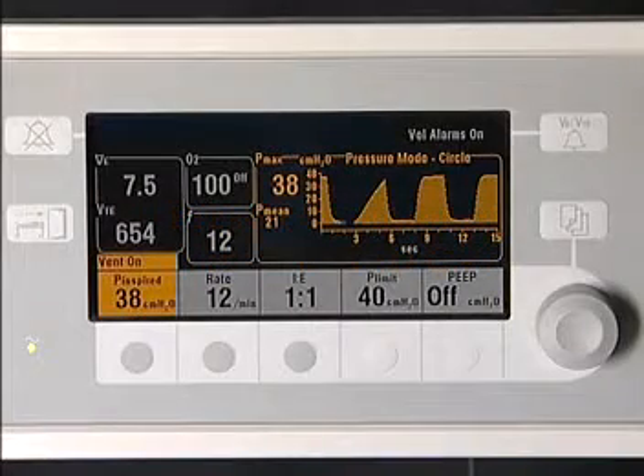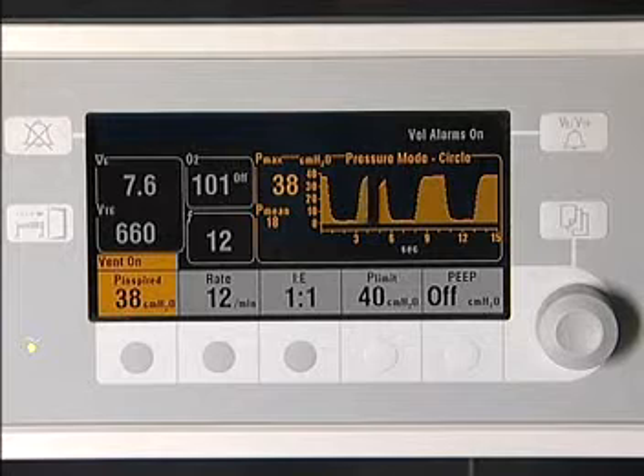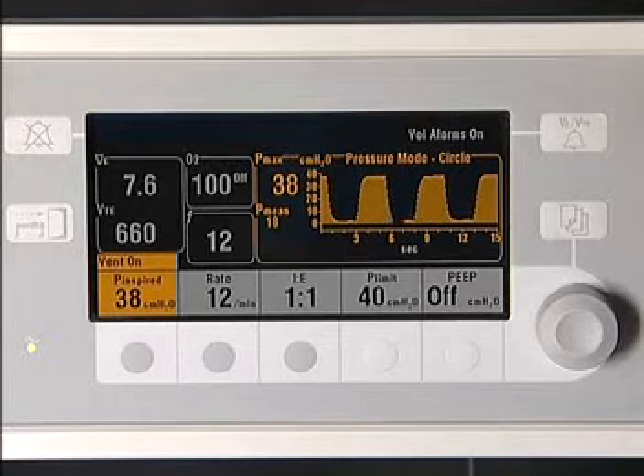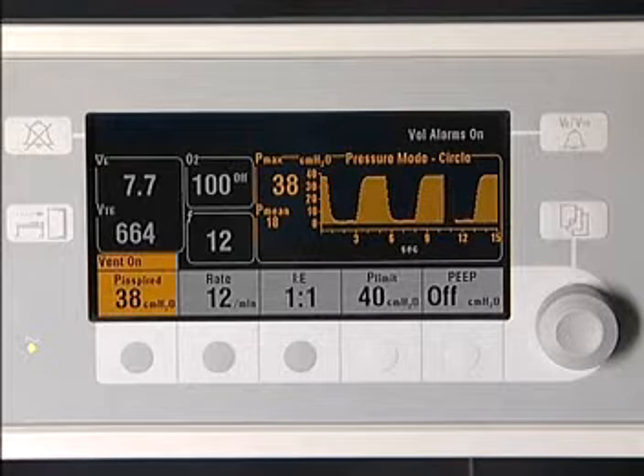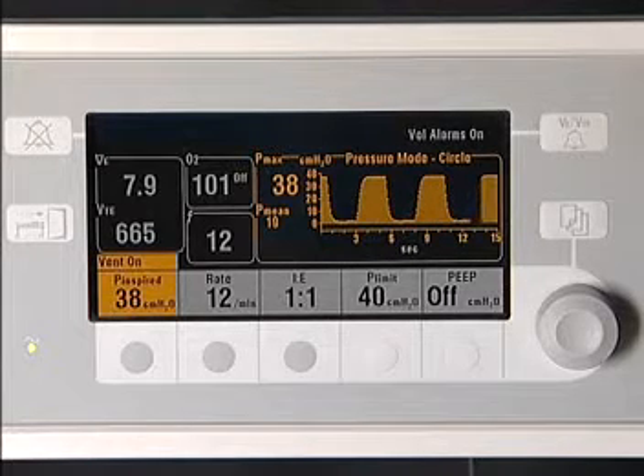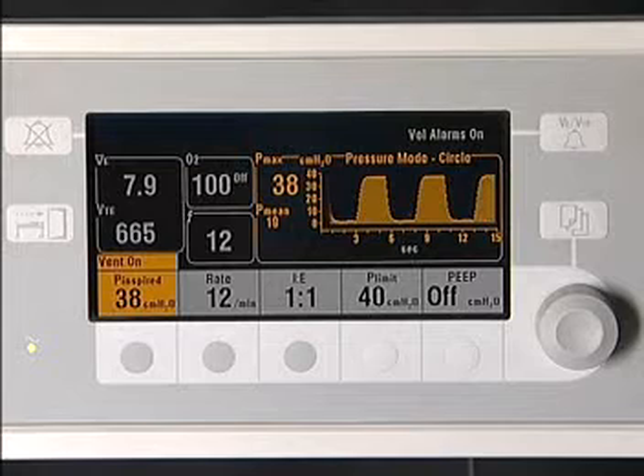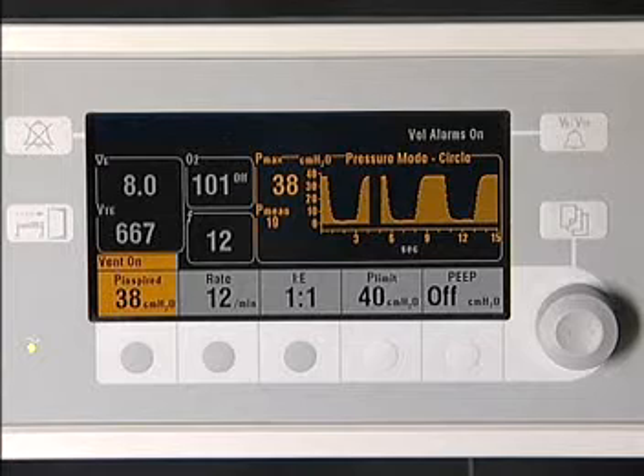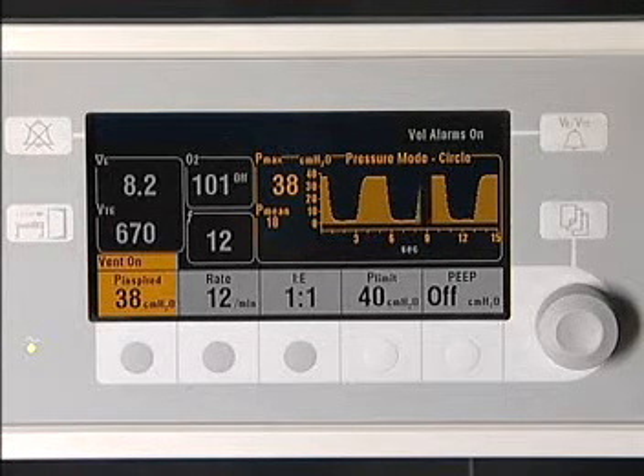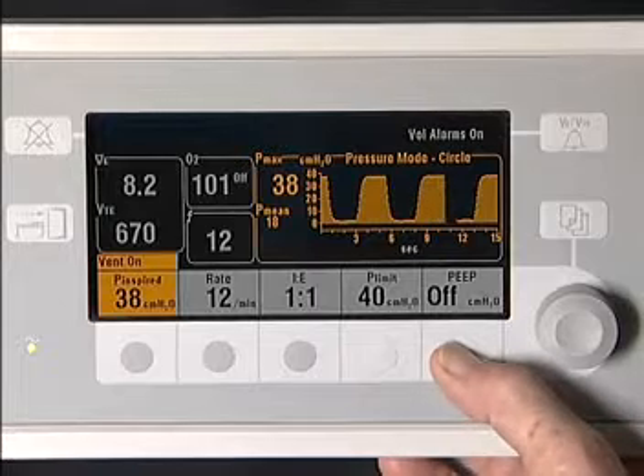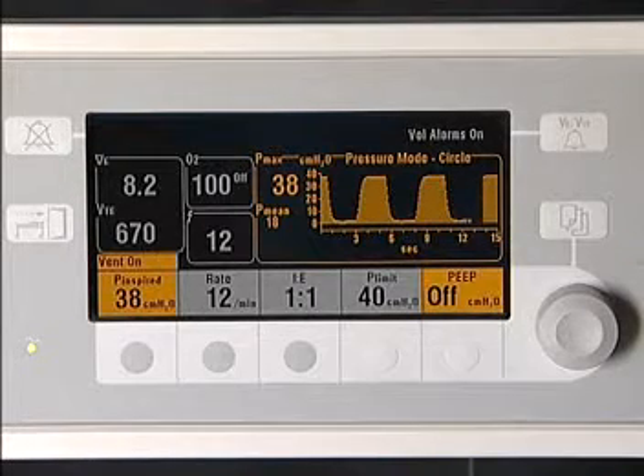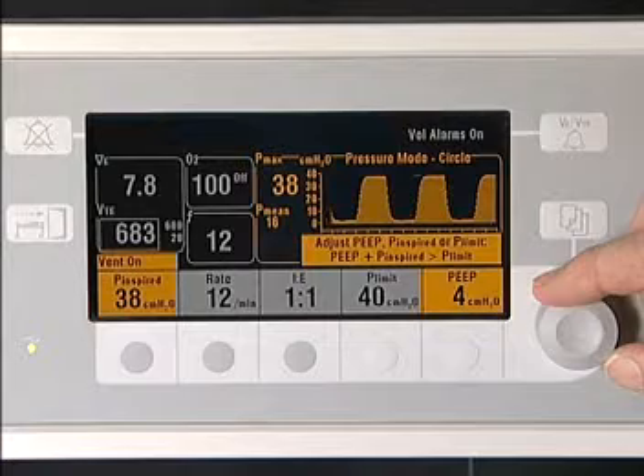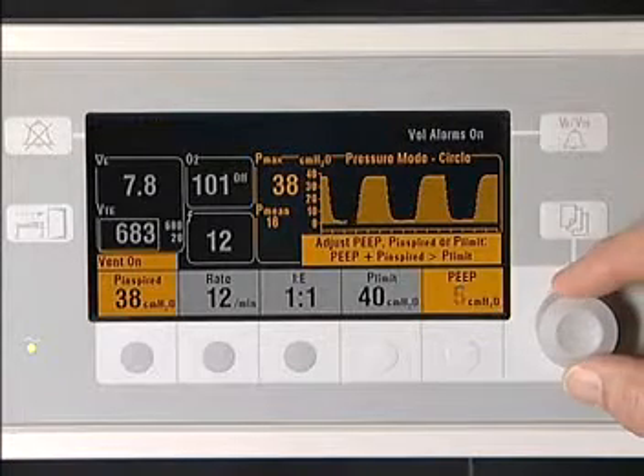Pressure control ventilation is a possible feature to use with leaking, uncuffed tracheal tubes, obese patients, or stiff lungs. An inspiratory flow rate as high as 120 liters per minute assures rapid movement through the dead space to the alveolar level. Pressure sensing every 4 milliseconds at the inspiratory sensor guards against overshooting the target inspired pressure. In pressure control ventilation, changes in compliance are automatically compensated for.